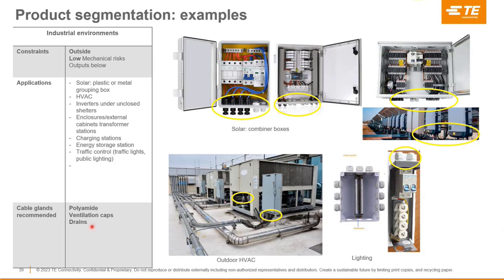What has to be noticed is that in this case you'll eventually need what you call ventilation caps and drains. These are specific cable glands that allow you to equalize the pressure within the panel between outside and inside, to avoid penetration and also condensation and moisture staying in the panel.